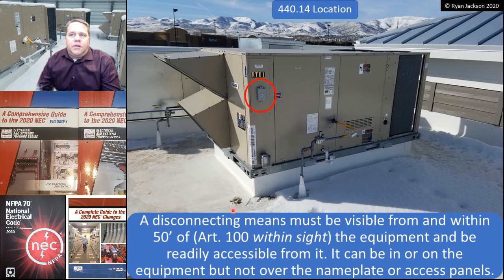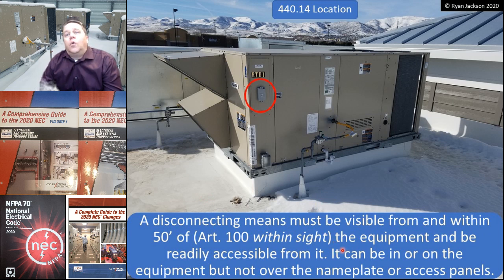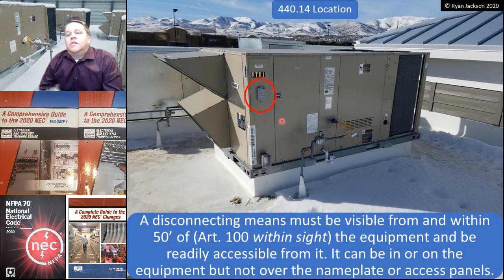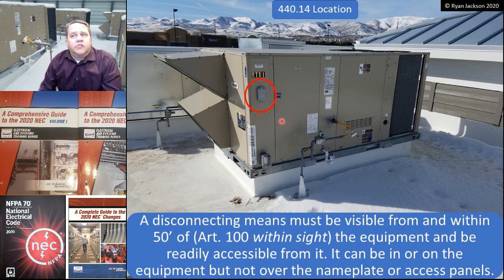It also has to be readily accessible from the equipment. So the disconnecting means must be within sight and readily accessible from the air conditioning equipment. It can be in or on the equipment, but not over the nameplate or any access panels. Here you can see that the disconnect is part of the unit — it's on the unit — and that's perfectly fine, as long as it's not over the nameplate or any access panels.